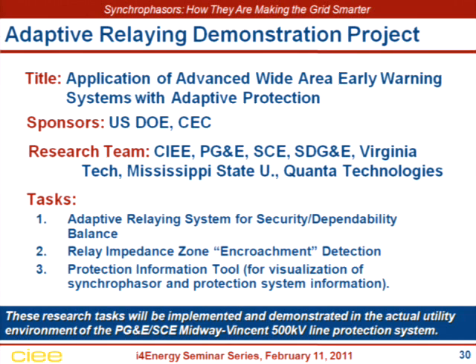The second is relay zone encroachment detection. And this is more not when something happens in real time, but as things evolve over time. As the system has more lines and generators put in or loads move around, more loads come on, more renewables, the relay characteristics should shift with that evolving scheme, but it doesn't. And so this just gives operators and protection engineers visual ways of seeing what's happening so they can say, maybe I need to go out and readjust that relay setting. I don't need to do it in real time, but I can do it in weeks or months.